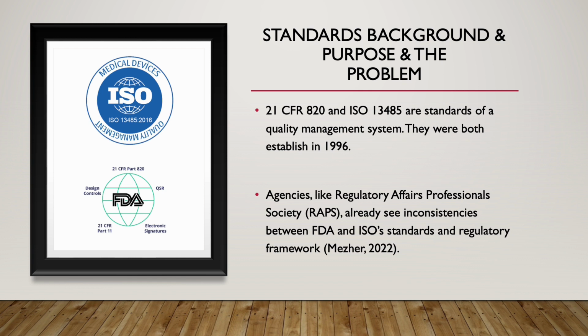Last year, the FDA announced they would be proposing a merger of the Device Current Good Manufacturing Practice requirements of the Quality System Regulation, 21 CFR 820, to align more closely with the ISO 13485 standard. If finalized, the long-awaited and long-delayed proposed regulation will rename 21 CFR 820 as the Quality Management System Regulation, QMSR, and will align U.S. good manufacturing practices with international norms. The effort is estimated to save medical device companies hundreds of millions of dollars in compliance costs.